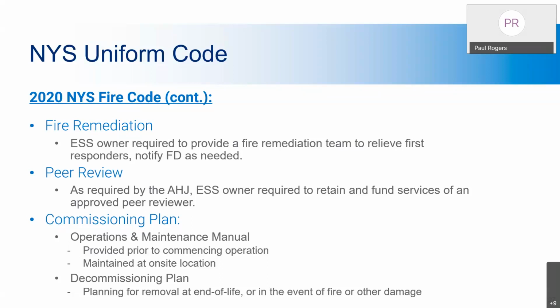Since it's very complicated and the UL 9540A data and testing report is extremely technical, the AHJ may have issues understanding it. So the code says if the AHJ requests a peer review to look at some of the stuff going in, whether it's the 9540A test or the installation itself, they can retain a peer review person to make sure these things are in properly. If there's anything outstanding, they'll have to address it with the installer.